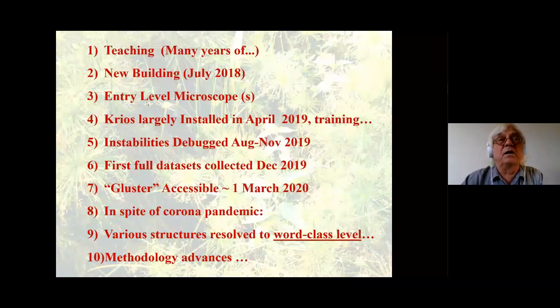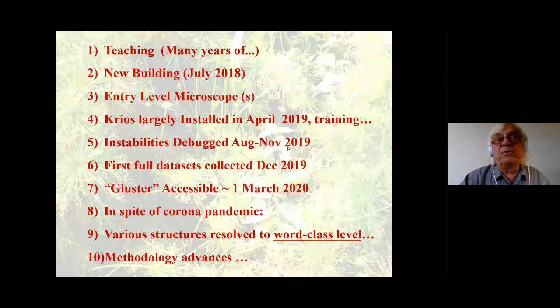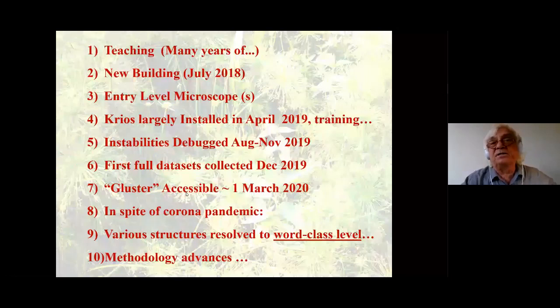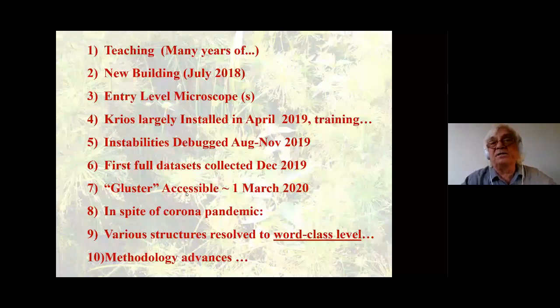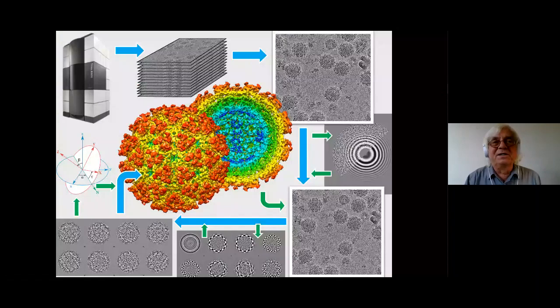There were already entry-level microscopes for cryo-EM to do low-resolution work and sample preparation. The Titan Krios was installed in 2018-2019 and after training the people, when we started to use it, it turned out to be totally unstable. Rodrigo and I spent at least four months debugging this beast to understand where the problems were. The first datasets were collected in December 2019, initially processed on home computers due to no available computer cluster. Since March, just at the beginning of the pandemic, we had a cluster available, and in spite of the pandemic we are now coming up with various world-class structures.